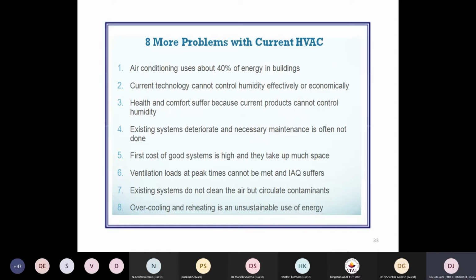Take the example of a split AC conventionally used in our homes and offices. It greatly affects the IAQ, which suffers a great deal. IAQ is the indoor air quality. What will be the quality of indoor air in terms of fresh air, cooling, humidity range, and velocity? Good filters should be located there. Most of the time in conventional HVAC, filters get clogged after prolonged service and may not be maintained properly. The infectants may then get circulated into the indoor environment.